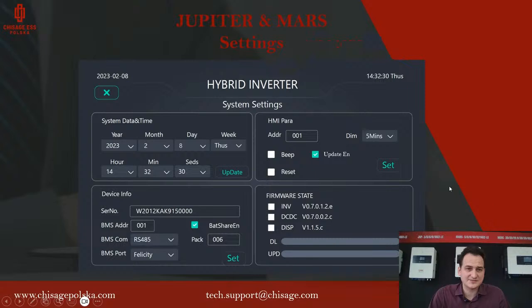For system settings, here we have the system date and time. At the left bottom, we have the battery communication settings. So we have BMS address for the BMS communication protocol, and BMS port. For BMS address, if we use RS485, we put 001. If we use CAN, it's 000. For BMS port, we pick the brand, basically which battery we use, with the protocol we use. So it's Felicity, or Chisage, or Pylon Tech, etc.